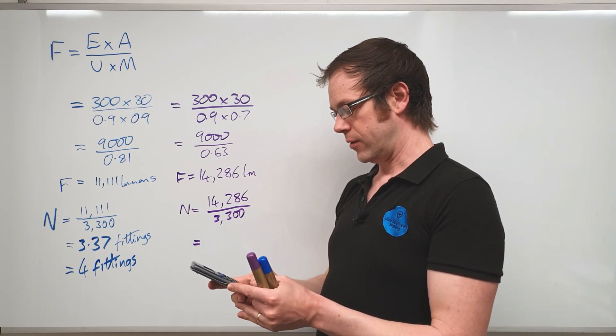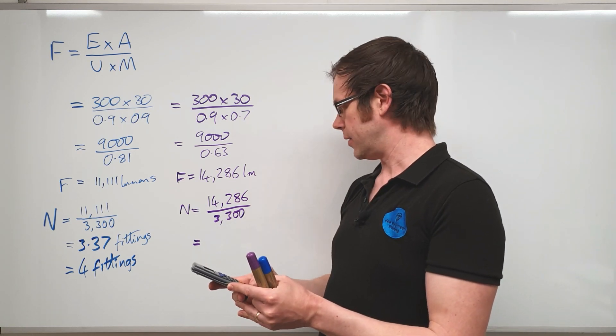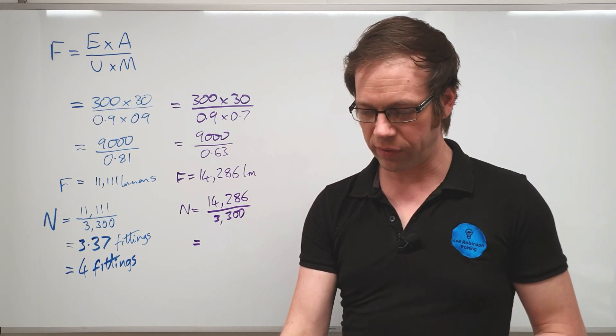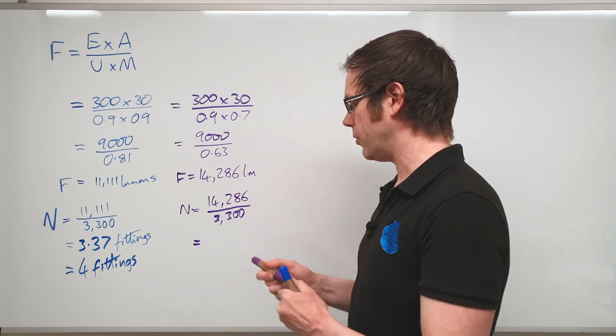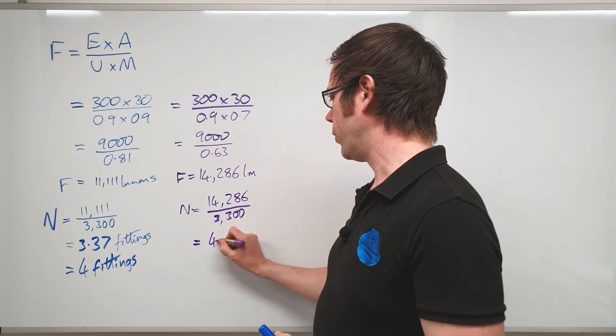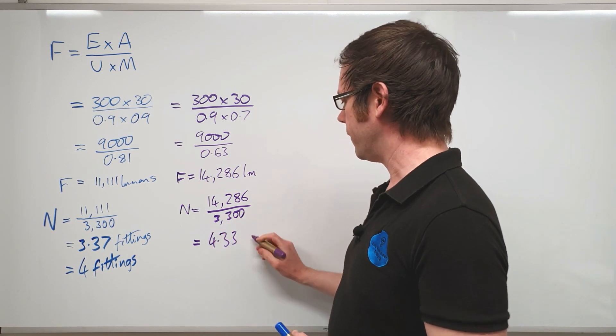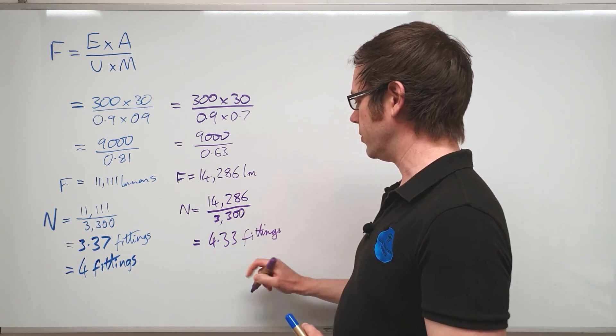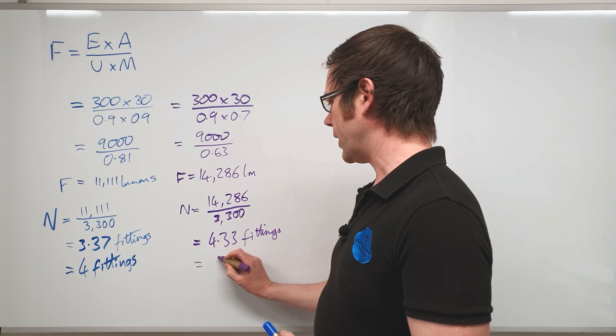And again when we do that calculation we come out with an interesting answer. 14,286 divided by 3,300, we come out with a value of 4.33 after we've rounded that. So we end up with 4.33 fittings. Now obviously that's nonsense, we can't install a third of a fitting, so that's going to get rounded up to five fittings.